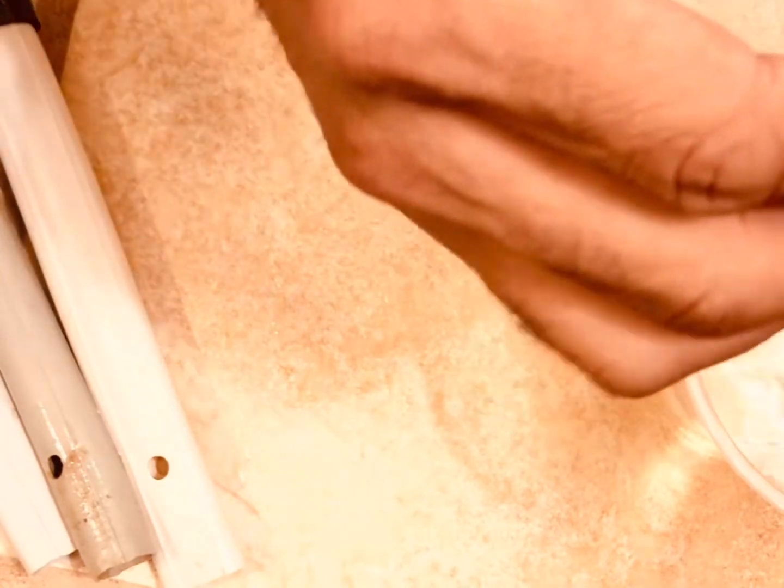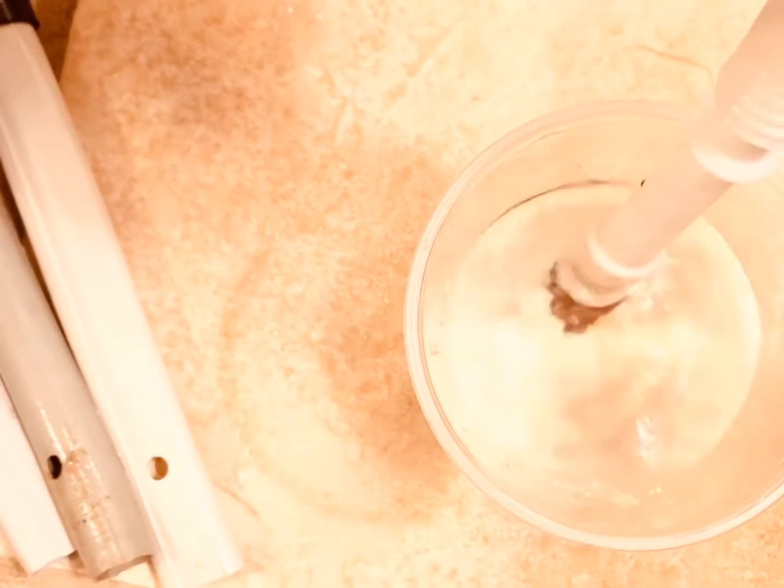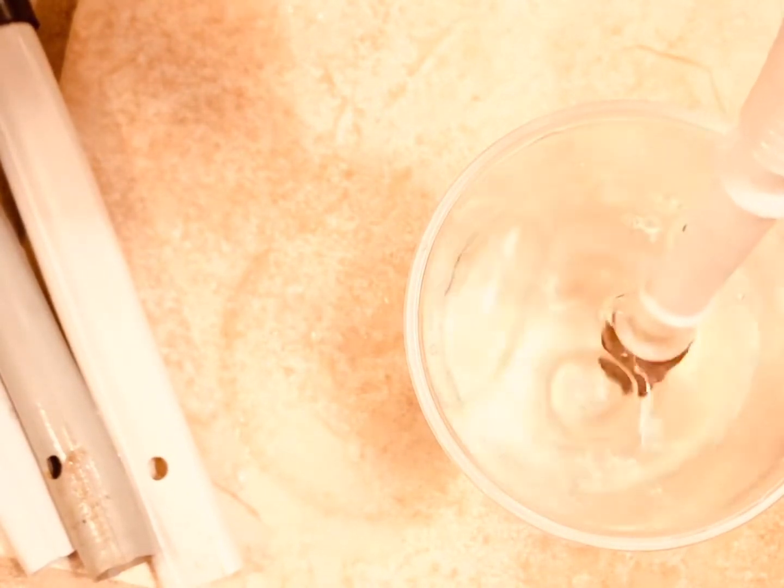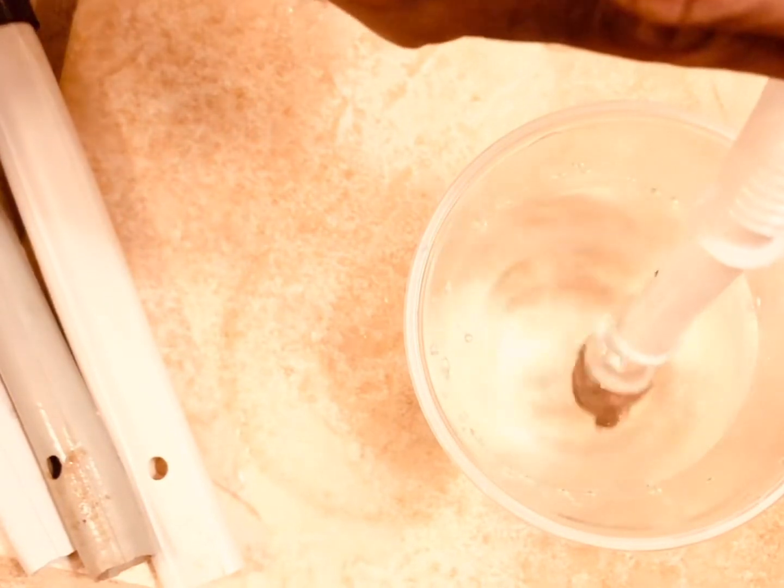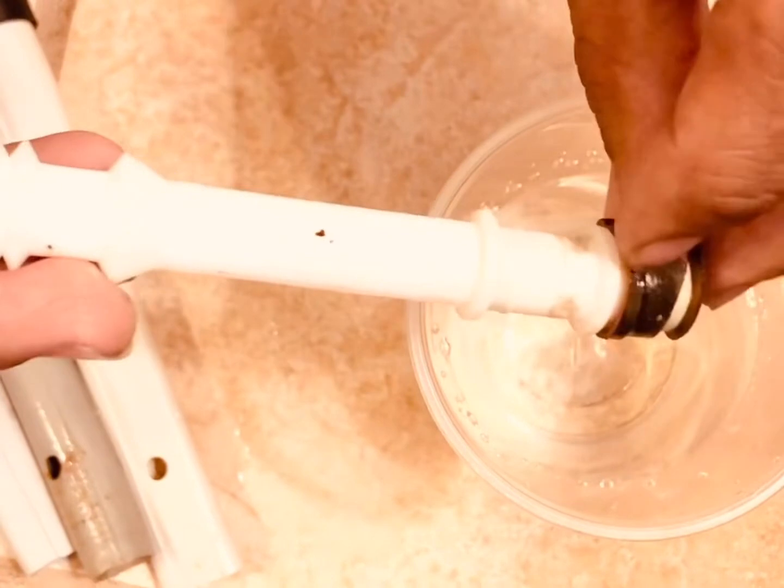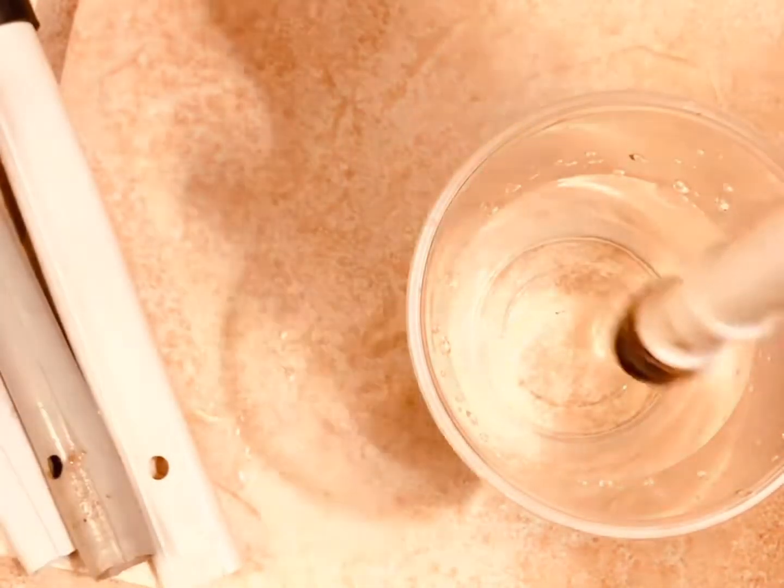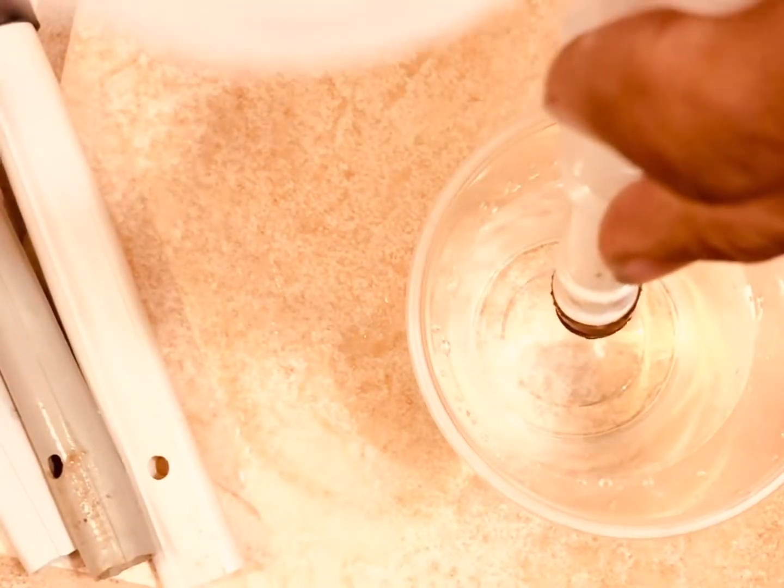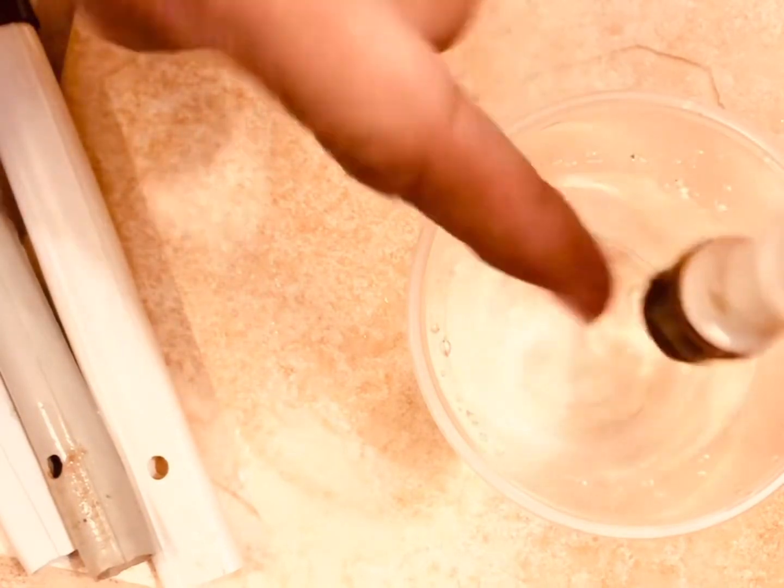Now let's say the fan is going, I'm simulating the fan now. See the water? I'm going to get a little suction. You know it's sucking in air, so that's why it's so important that you have a seal, because there's a suction going on. Obviously the vacuum is a little bit stronger than the fan, so you want to have a little bit of space for the air to circulate. This is like a one-way flap, opens and you have a pretty good seal. It allows the water to flow through and almost hold a little bit of water as a seal.